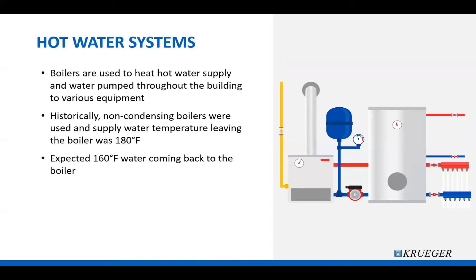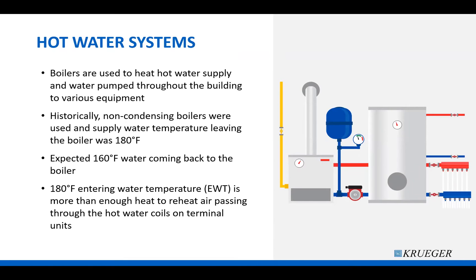That means 20 degrees of the water was used for heating at the thermal units and other equipment. This 180-degree water temperature provided enough heat to reheat air passing through the terminal unit. The supply air temperature through a single duct terminal unit is usually around 55 degrees, so that 125-degree difference between the water and the air allowed heat transfer to happen rapidly at the water coil.